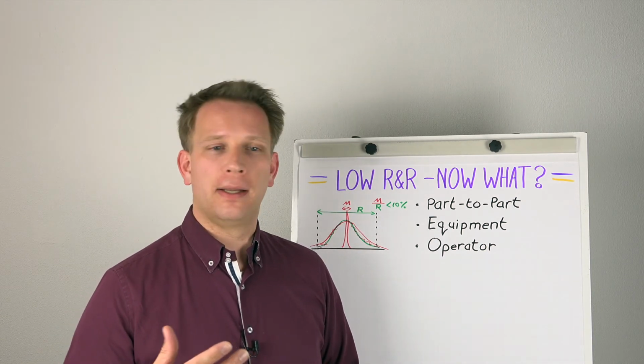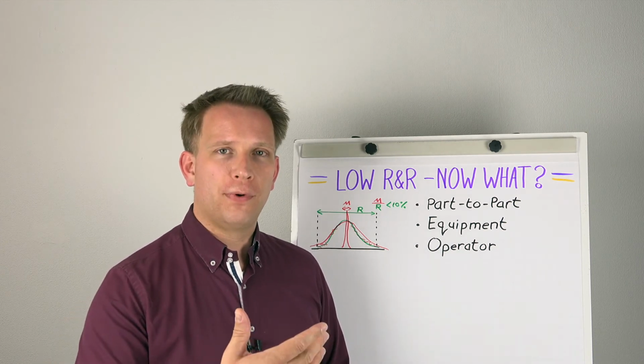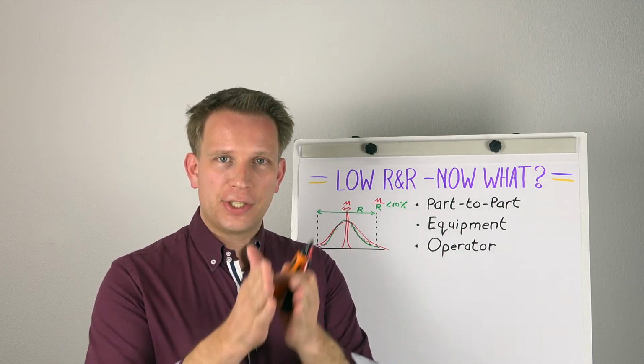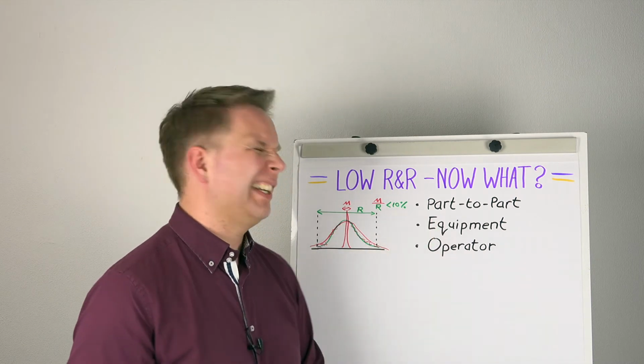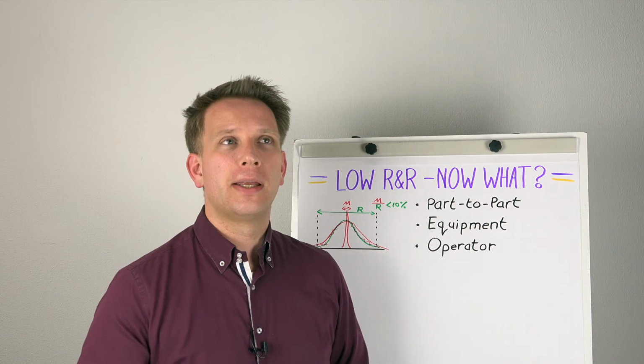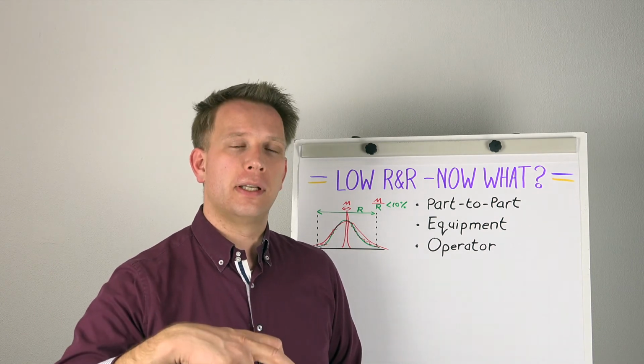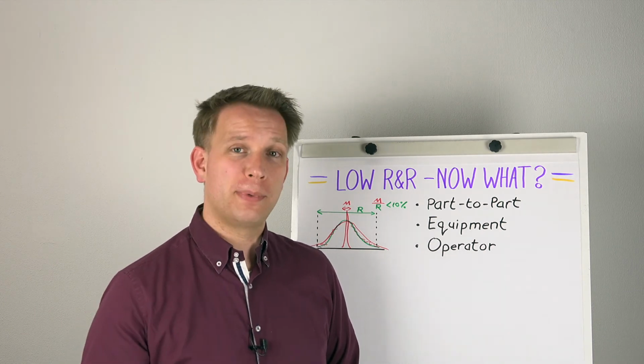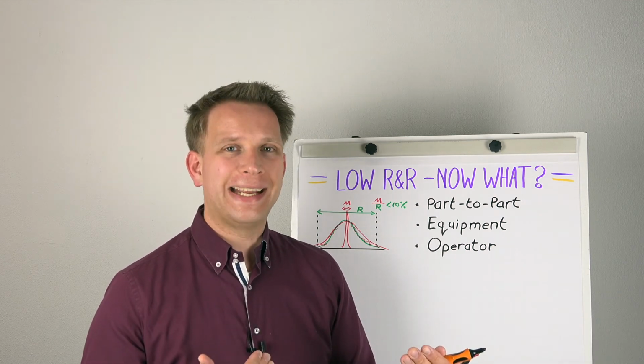And if you see that 2 or 3 out of your 5 have really nice, very tight equipment variances, so very small equipment variances, and the others do not, then check: are these the people that are better trained or more experienced? Then you have a training gap.